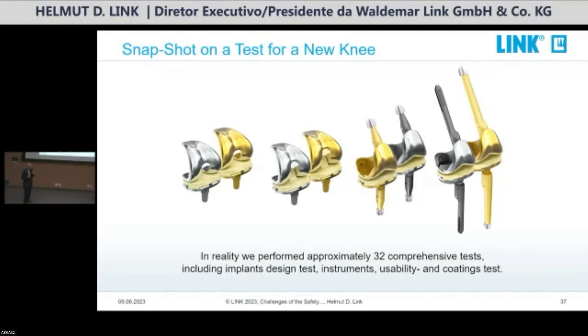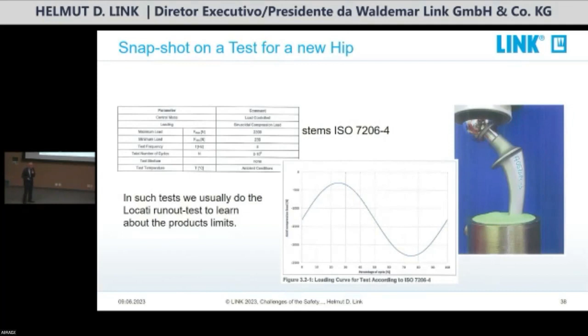For instance, when we test a new stem, we don't do only the ISO 7206-4, the test which is necessary for a hip stem, but I always want to see the so-called Locati runout test. The Locati test means we step up with our testing until the implant fractures. From that, I get the information, how strong is that? Is it only a little bit above the requirement, or is it a long way above the requirement? I want to know that.